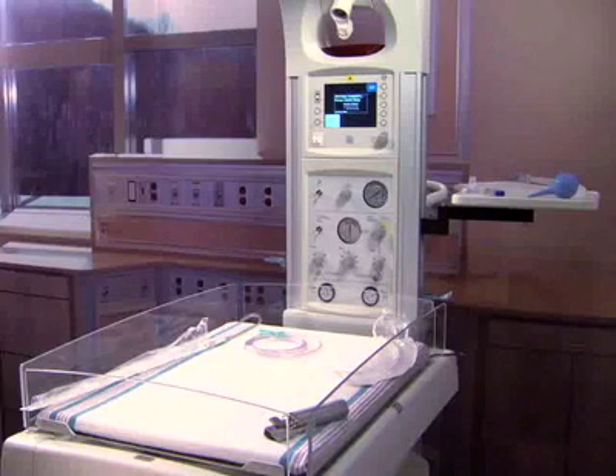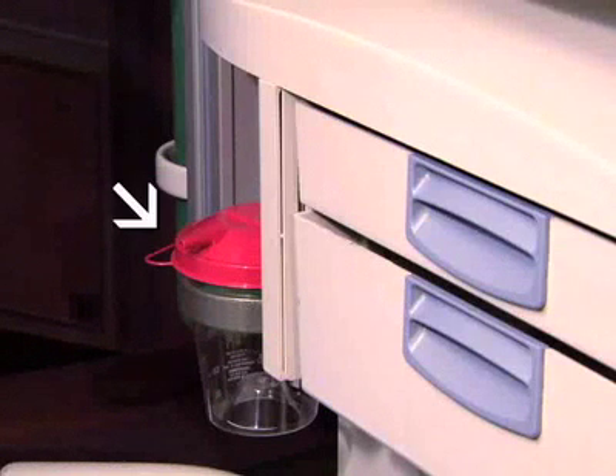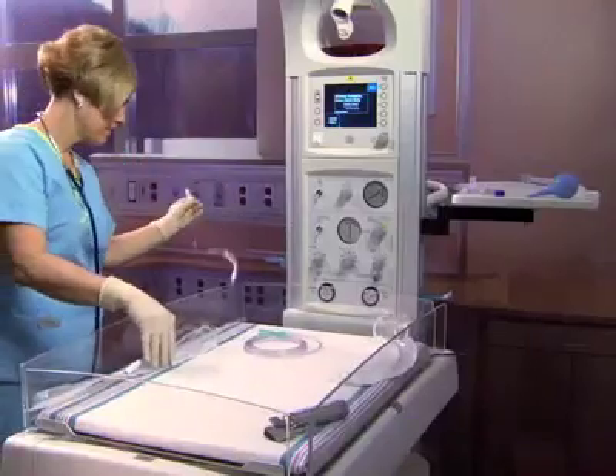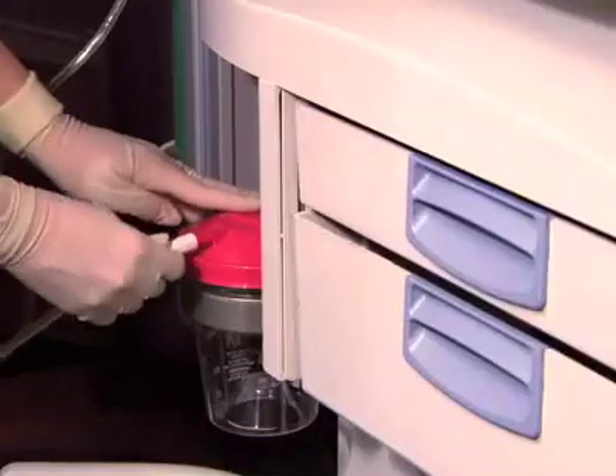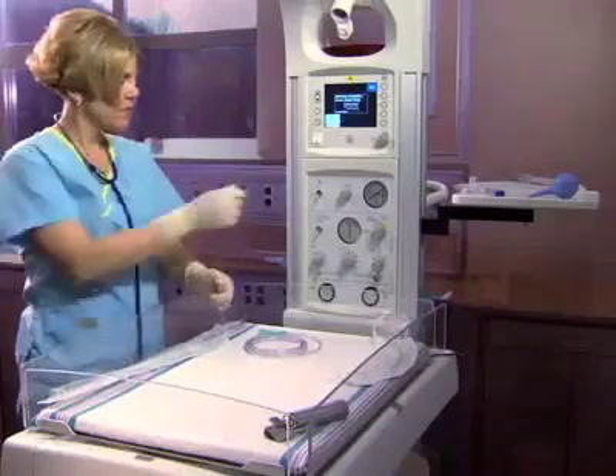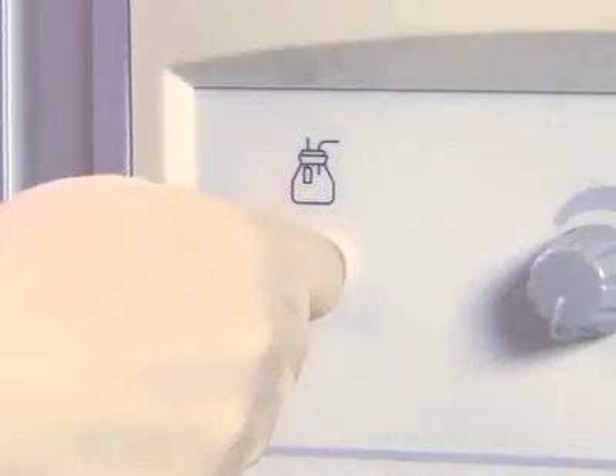Next, perform the checkout procedure for the suction. Check that a clean suction canister is properly installed and attached to the tubing in the dovetail rail. Attach desired length of suction tubing to the suction canister. Turn the suction control switch on.